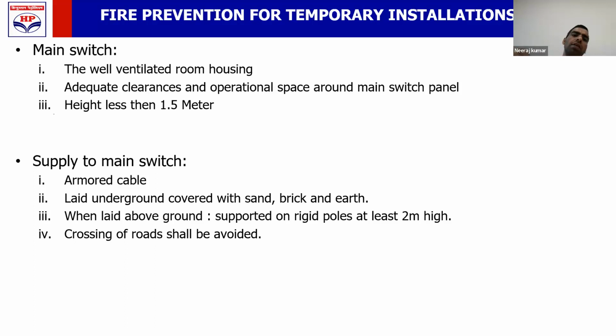So the main switching station of the temporary supply shall be in a well ventilated housing. You should not keep your temporary supply main switch in an open area. You should also keep adequate operating space around this main panel.